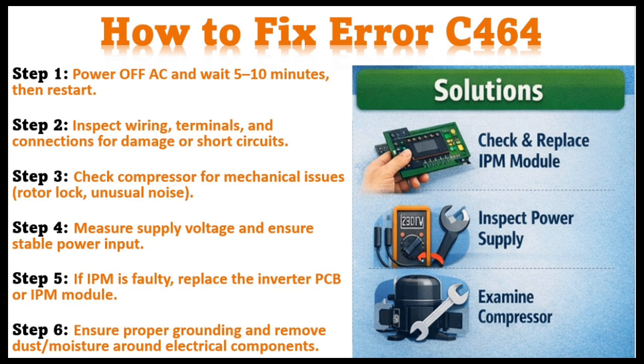Step 3. Check the compressor for mechanical issues, such as a locked rotor or unusual noises. Step 4. Measure the supply voltage to ensure a stable and proper power input. Step 5. If the IPM is found to be faulty, replace the inverter PCB or the IPM module.